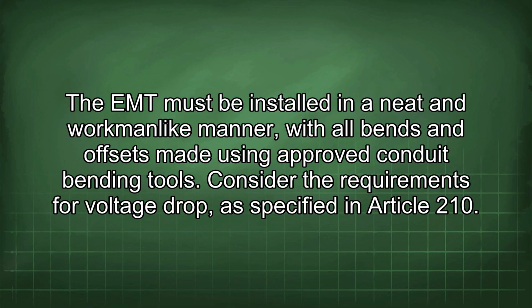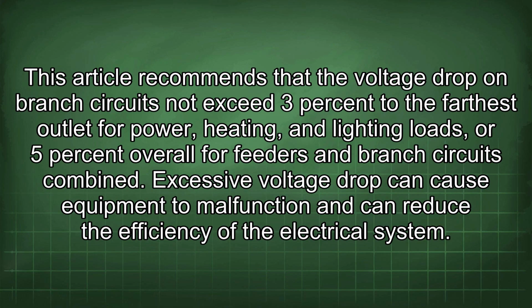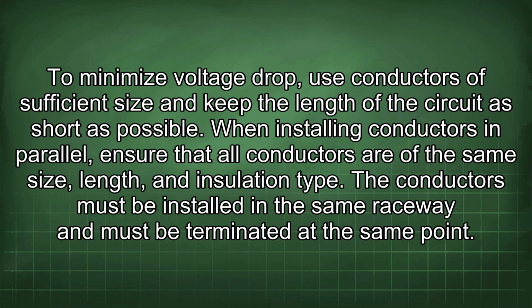Consider the requirements for voltage drop, as specified in Article 210. This article recommends that the voltage drop on branch circuits not exceed 3% to the farthest outlet for power, heating, and lighting loads, or 5% overall for feeders and branch circuits combined. Excessive voltage drop can cause equipment to malfunction and can reduce the efficiency of the electrical system. To minimize voltage drop, use conductors of sufficient size and keep the length of the circuit as short as possible.